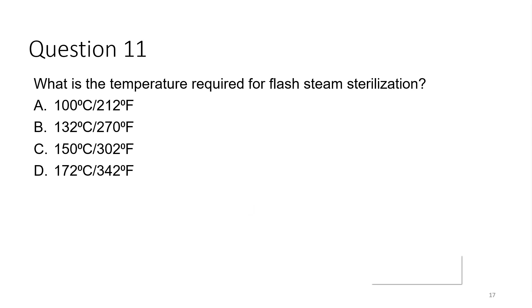So flash is kind of outdated. We really call it IUSS now, immediate use steam sterilization. Like, do people still say flash? Yeah, absolutely. But it's a term that we're trying to move away from, towards immediate use steam sterilization, which is IUSS. So flash steam sterilization was originally defined by Underwood and Perkins as sterilization of an unwrapped object at 132 degrees Celsius for 3 minutes at 27 to 28 pounds of pressure in a gravity displacement sterilizer.